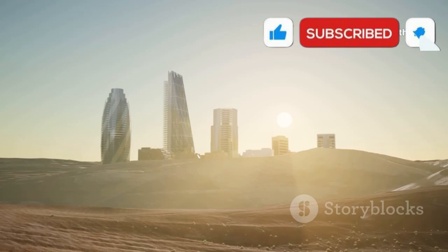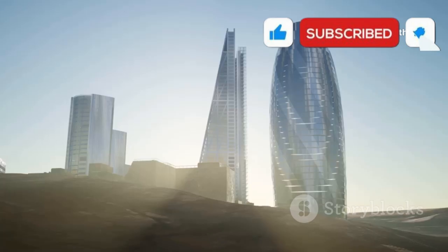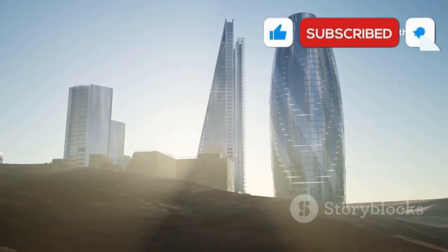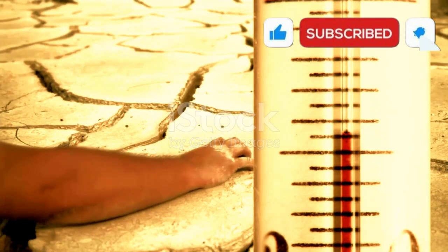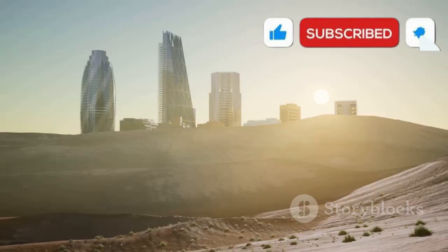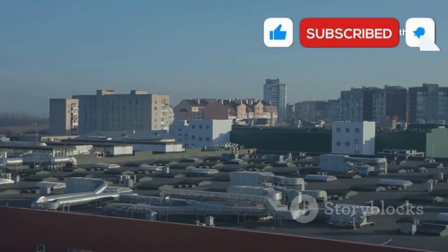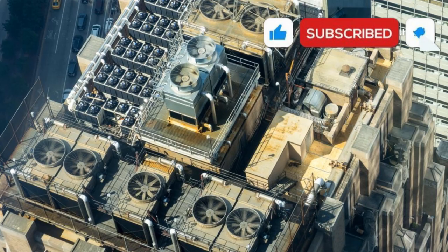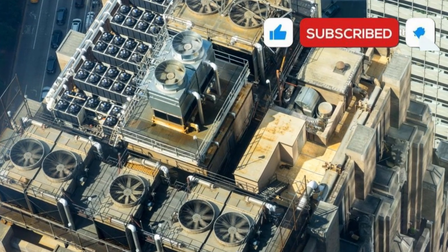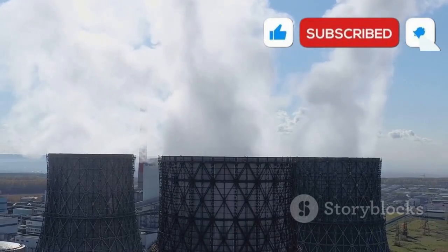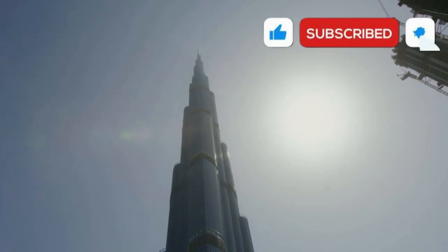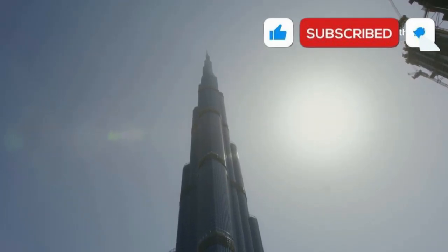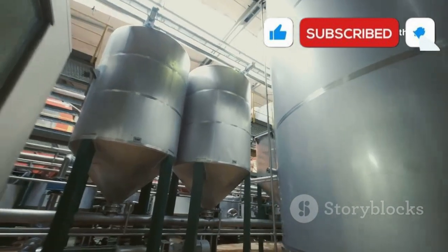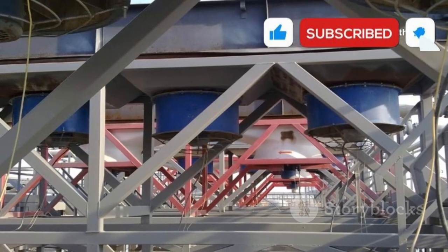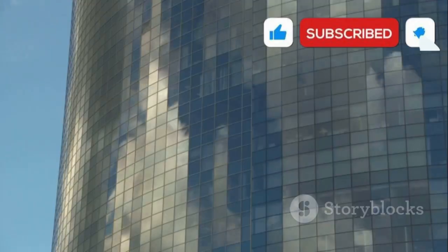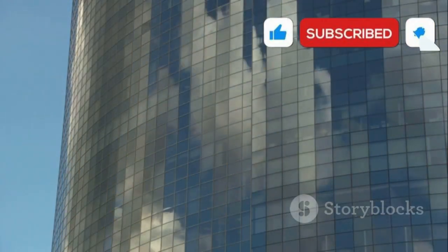First stop, the desert. In desert cities like Dubai, skyscrapers face extreme heat and dry air. Daytime temperatures can soar above 45 degrees Celsius, 113 degrees Fahrenheit, and the sun beats down relentlessly. Powerful chillers work non-stop to keep buildings cool. Dry air makes evaporative cooling in rooftop towers especially effective. Water evaporates, taking heat with it. The Burj Khalifa system can handle cooling loads equal to melting 13,000 tons of ice per day. To save energy, it uses ice storage, making ice at night, then melting it during the day to help cool the building. High-performance glass reduces solar gain, keeping interiors cooler.